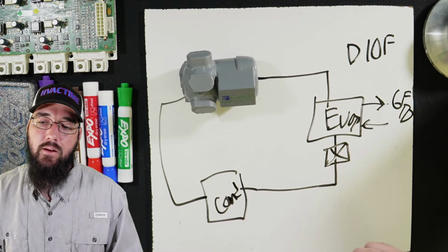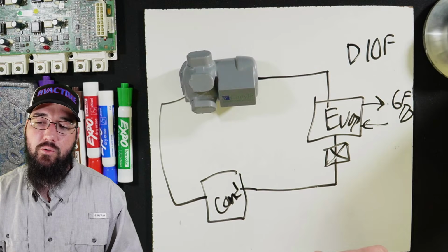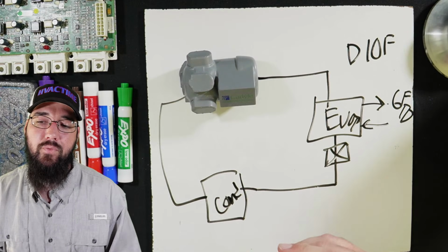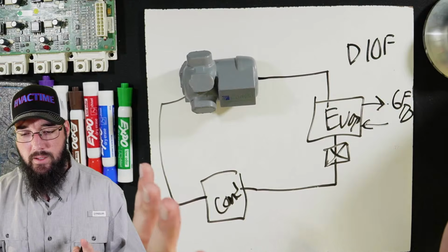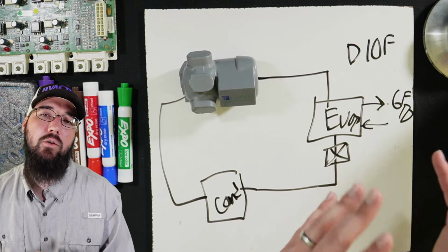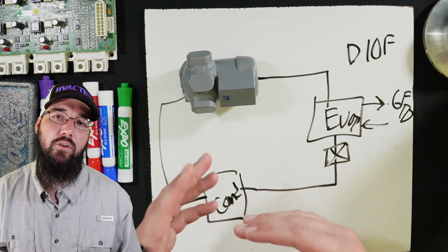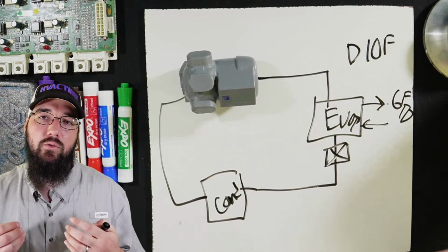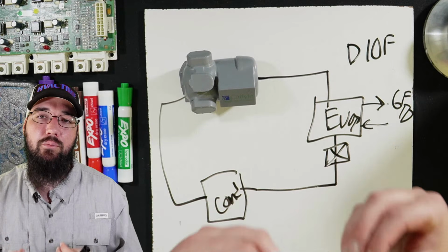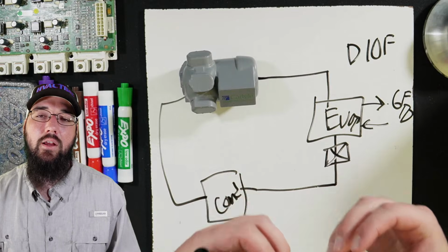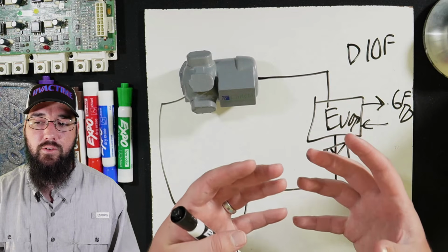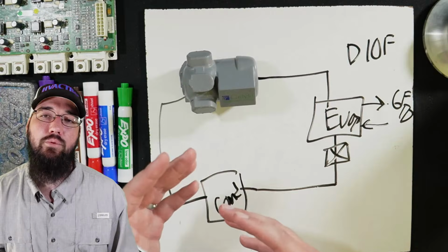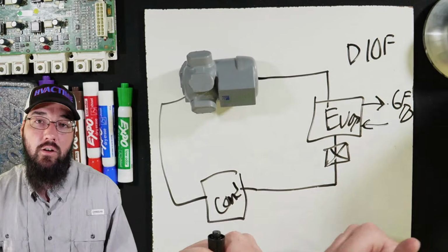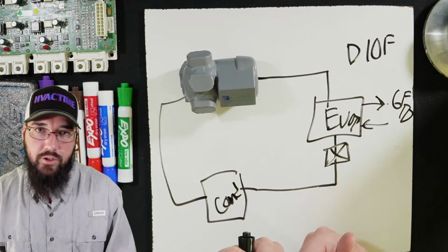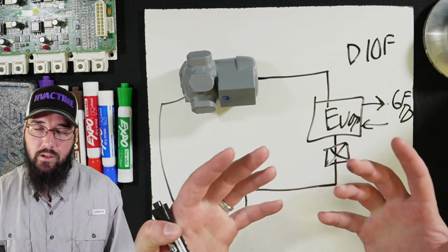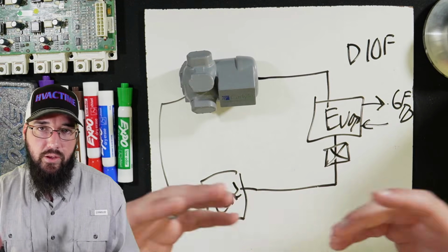Yeah. So is that why they say screws are... Well, so all compressors... All right, so it's not quite that simple, all right? All compressors, ultimately, as you lower the load, what's really important is lowering the compression ratio on the compressor. That's what's important for the compressor itself. We want to get a lower compression ratio, which usually when we're unloading the compressor, compression ratio lowers with it, typically, and things become more efficient.